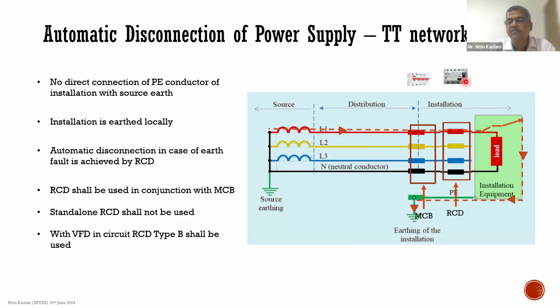Again, since in modern day elevators we have the variable frequency drives connected in the circuit, we should use RCD type B only. Please do not use any other RCDs, RCD A, RCD AC, or RCD type F in the circuits here.